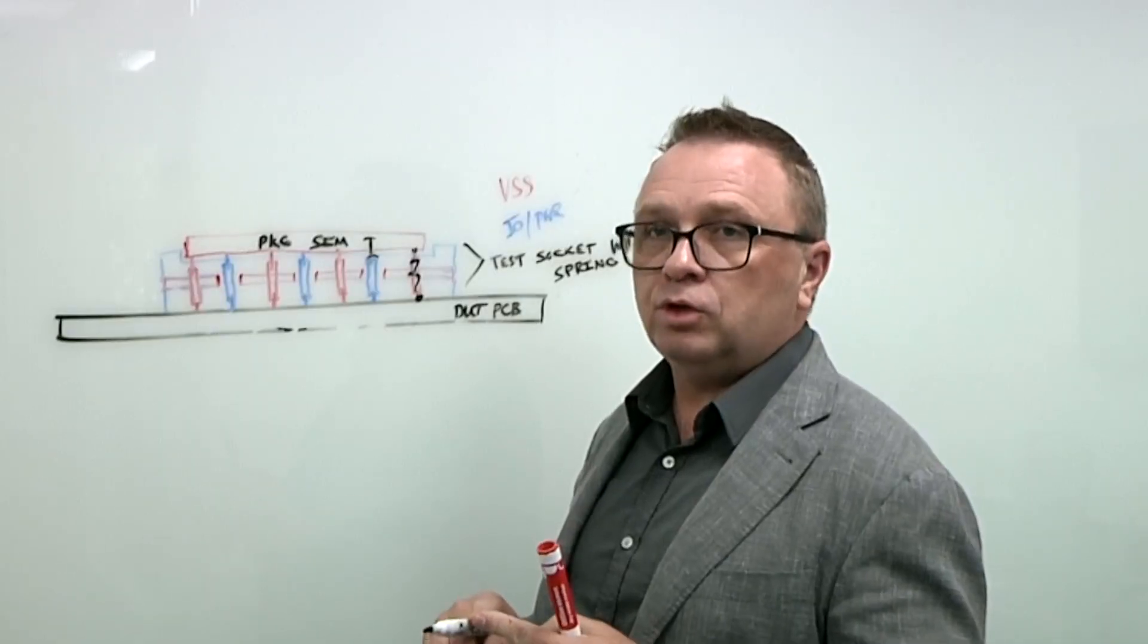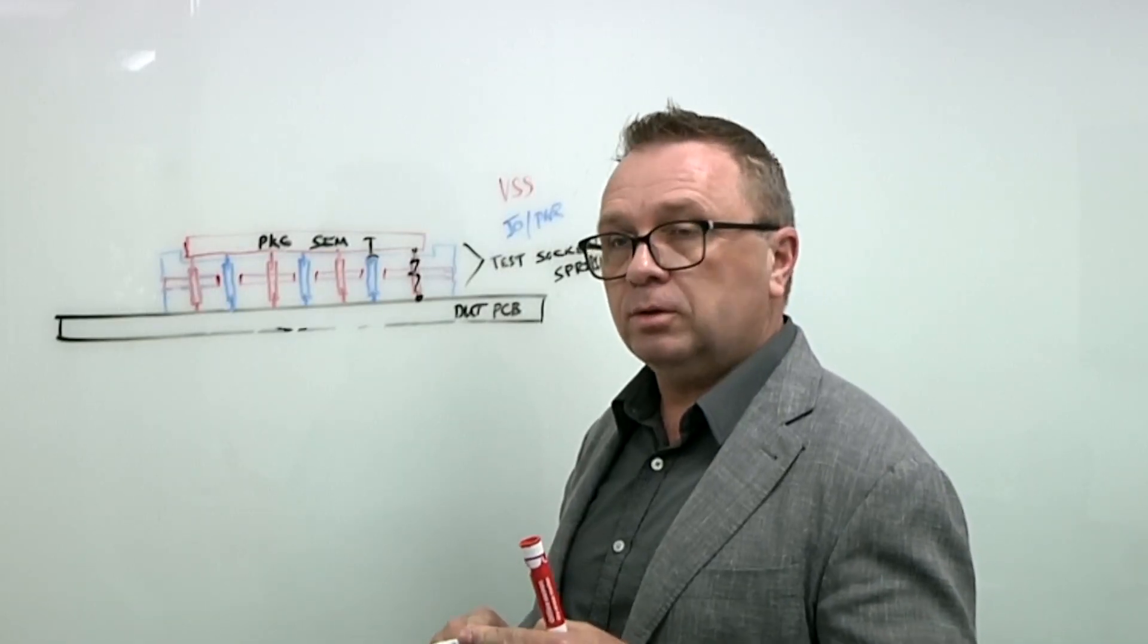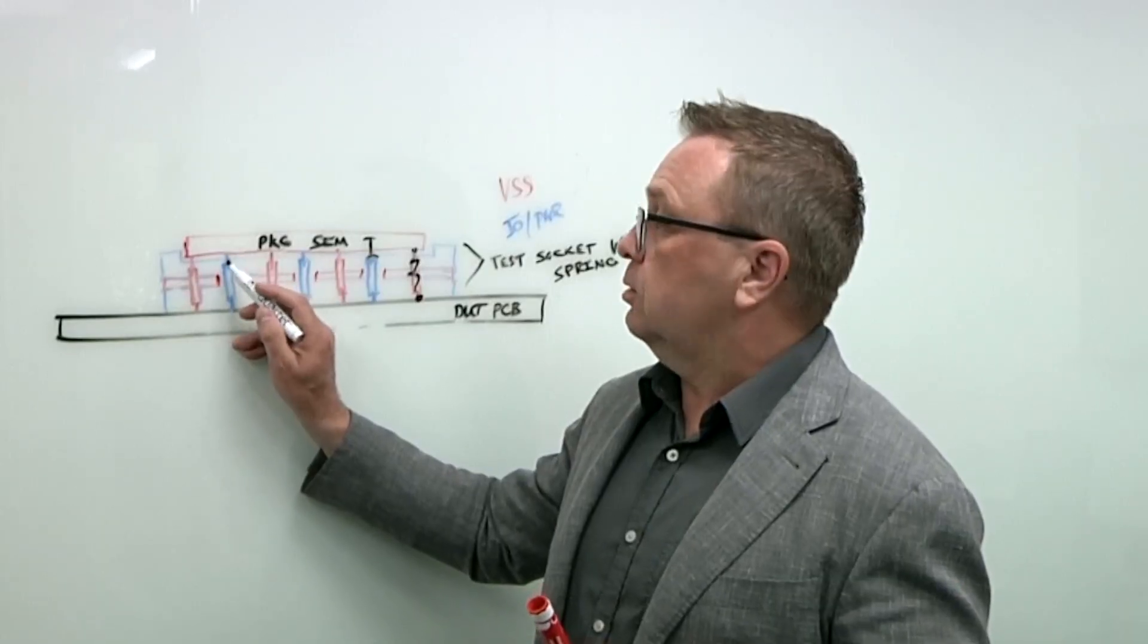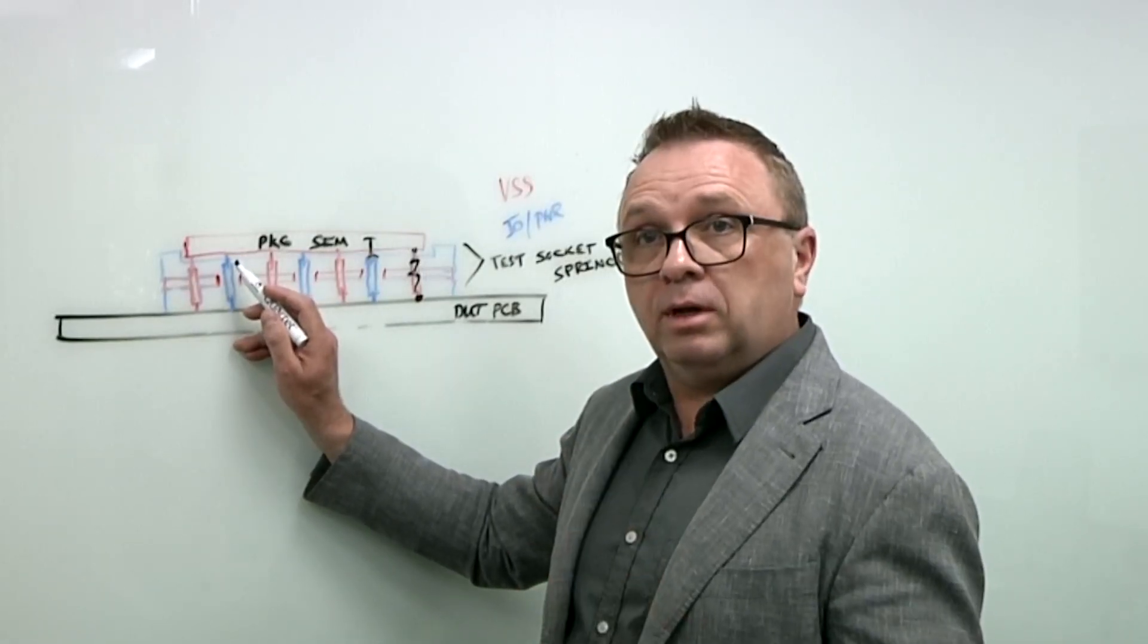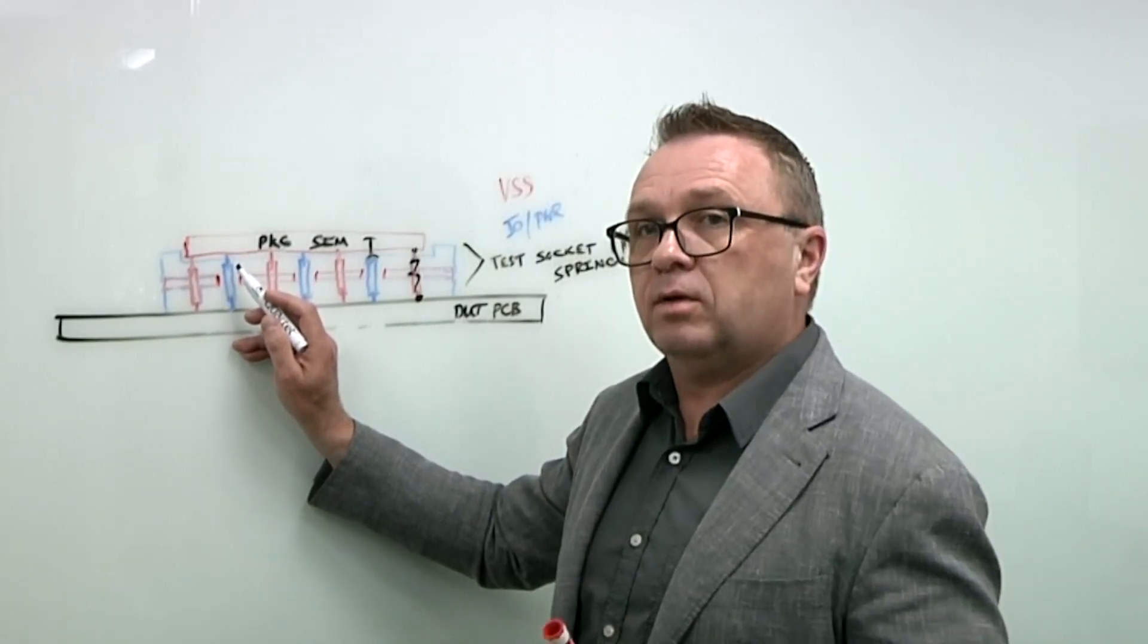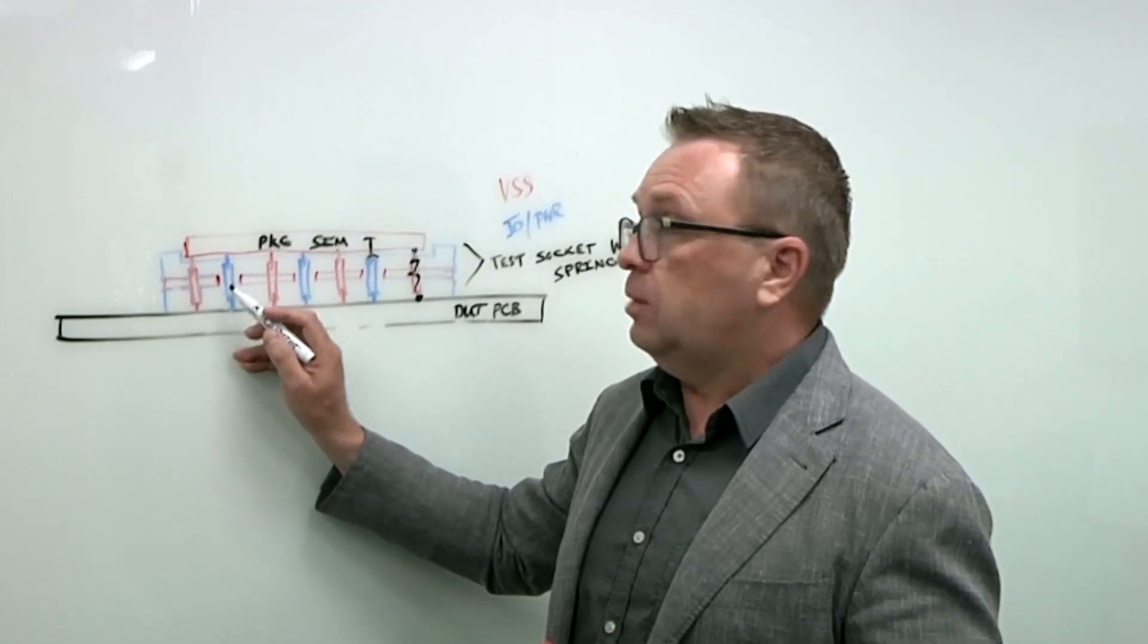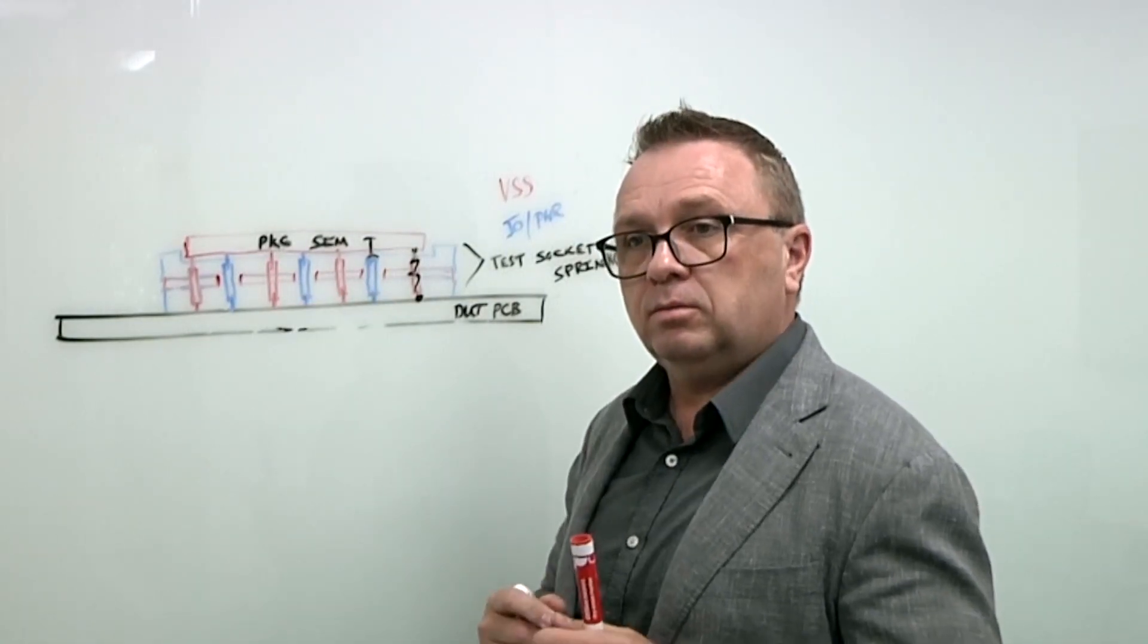Which may diffuse the ball material onto the plating of the pin and degrade the contact resistance. So those are the kinds of things that we're looking to measure so that we can replace the pins as needed to keep the performance where it needs to be.